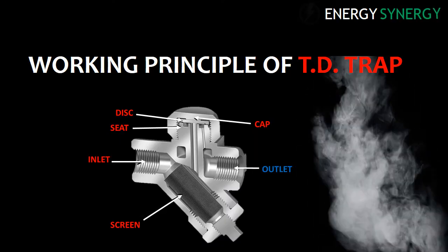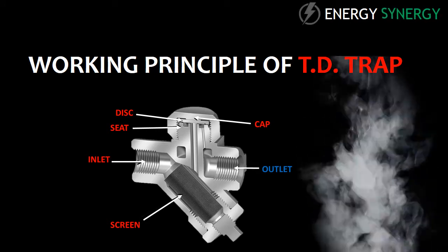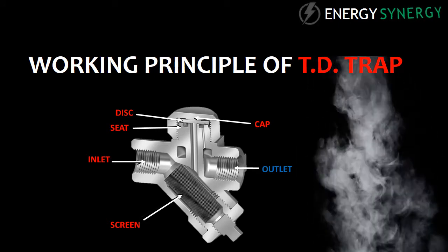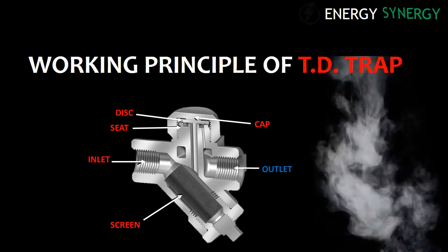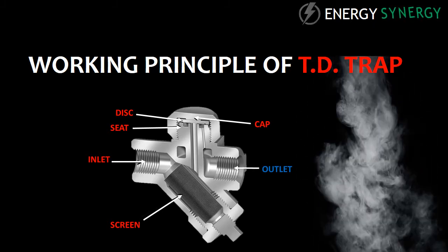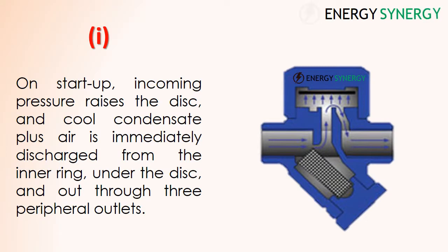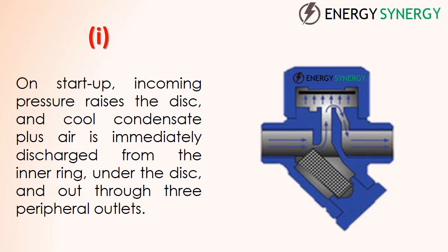A cap is situated on top of the trap which consists of a disc and a seat inside it. TD traps work in four stages, each explained with an animated steam trap. Stage one: on startup, incoming condensate pressure raises the disc, and cold condensate plus air is immediately discharged from the inner ring under the disc and out through three peripheral outlets.